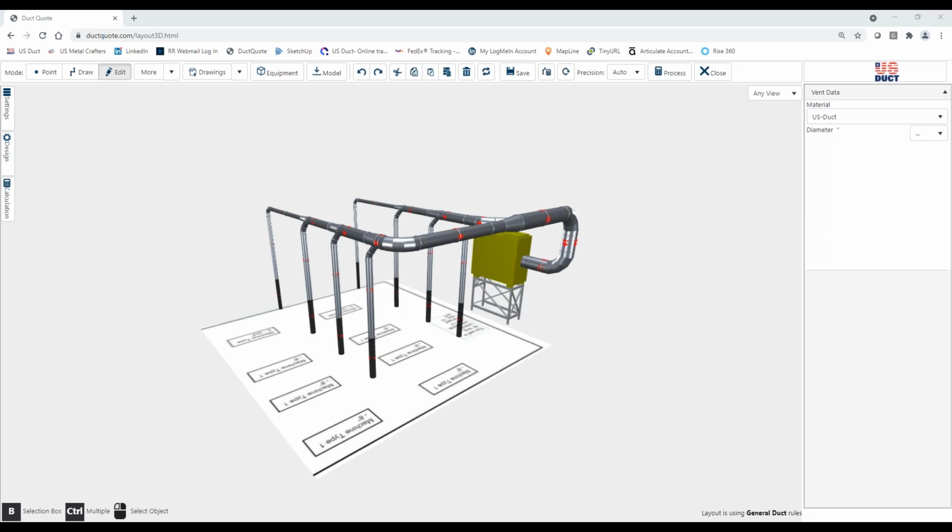Now on a multiple branch system with no gates or dampers, each branch of the ductwork is going to have a different restriction to flow. So longer or smaller diameter duct runs will have more restriction, where shorter, larger diameter duct will have higher flow. And that's true so that they're probably going to be off their intended share of the airflow load.